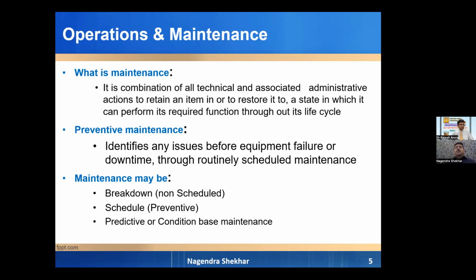Whereas non-scheduled maintenance is breakdown maintenance. When a machine or system has stopped working, it is out of operation because of anything, then you have to make efforts, collect everything and put that machine or system into operation. So basically in a power distribution system, any breakdown means a failure to supply electricity to the end consumer. So when it happens, you have to ensure that everything is set right and the power is restored to the consumer. And third is predictive or condition based maintenance.